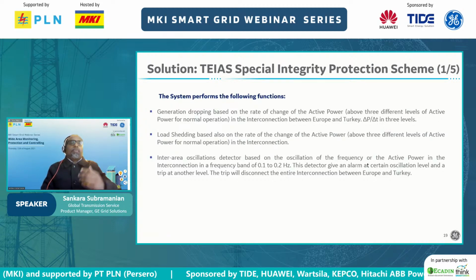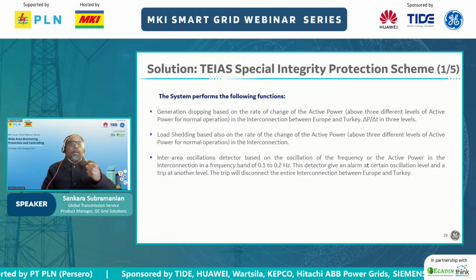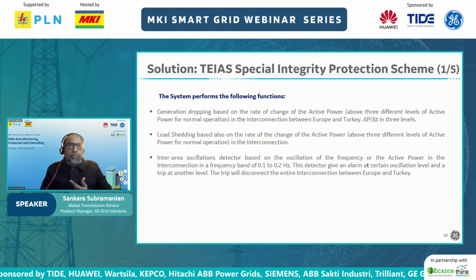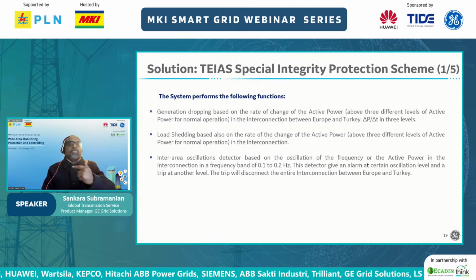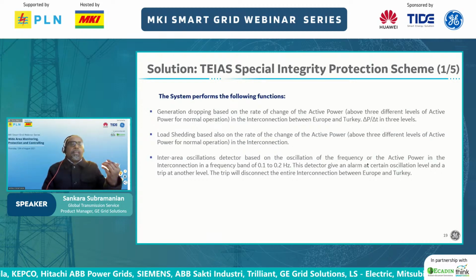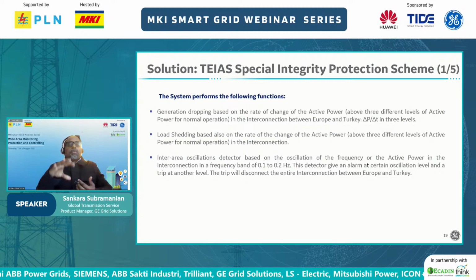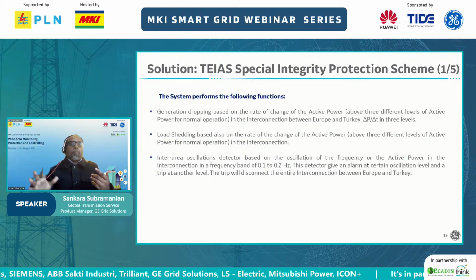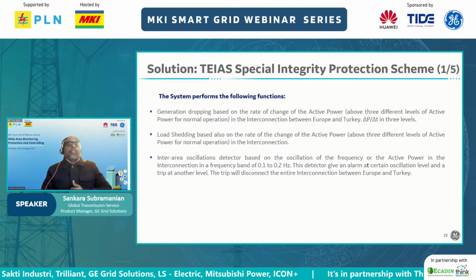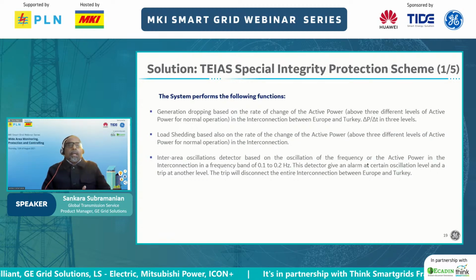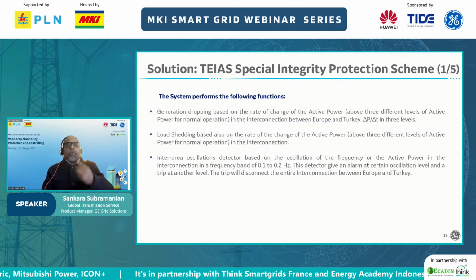Following this, the system had generator dropping, based on the rate of change of active power, in this interconnection between Europe and Turkey. If anything were to happen, Turkey had to do the generator dropping. Similarly, load shedding had to be carried out based on the rate of change of active power.